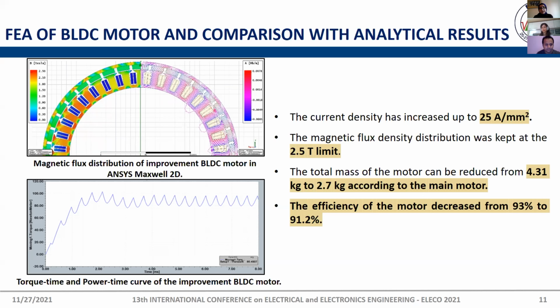Therefore, we increased the electrical load of the motor to 25 ampere per millimeter squared. And while doing this, our basic requirements were essentially the same. We changed the inner diameter of the motor and the dimension of the slot, while our basic dimensions, the rotor diameter and the winding properties, stayed the same. When the developed model is run with Maxwell 2D again, we can meet the 75 Newton meter value. We can reach the speed we want. We don't get saturation in the motor. This actually reduced the weight of the motor.